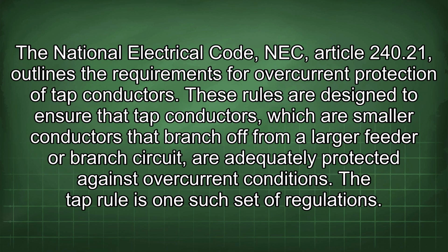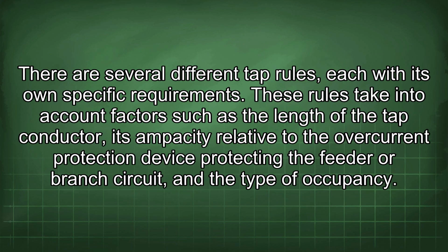The National Electrical Code (NEC) Article 240.21 outlines the requirements for overcurrent protection of tap conductors. These rules are designed to ensure that tap conductors, which are smaller conductors that branch off from a larger feeder or branch circuit, are adequately protected against overcurrent conditions. The tap rule is one such set of regulations. There are several different tap rules, each with its own specific requirements. These rules take into account factors such as the length of the tap conductor, its ampacity relative to the overcurrent protection device protecting the feeder or branch circuit, and the type of occupancy.